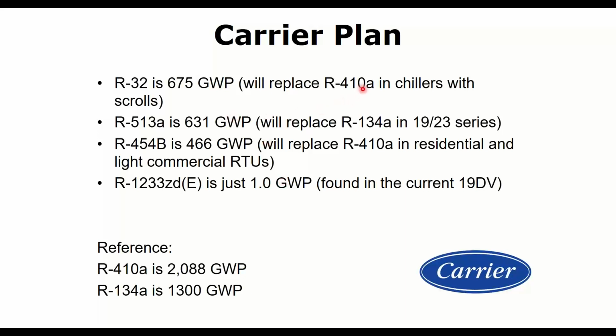For the scroll chillers with R410A, the replacement refrigerant is going to be R32 because it has a lower global warming potential, as mentioned earlier. For the big stuff with 134A—the 19 series chillers, the 23 series tri-rotor screw chiller—those are switching to R513A. It has properties similar enough to 134A that it'll allow the reuse of certain components when they manufacture these, not all, but some.